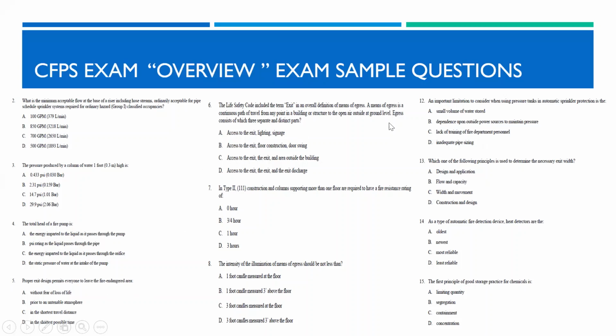Life safety means of egress means access to exit, exits, and exit discharge. If you are using type 2 construction with a column supporting more than 1 floor, fire resistance should be a minimum of 1 hour. For example, intensity of illumination at the means of egress should be 1 foot-candle at the floor level. An important limitation to consider when using a pressure tank in a sprinkler system is the small volume of water storage. Which one of the following principles is used to determine necessary exit widths? It should be flow and capacity.